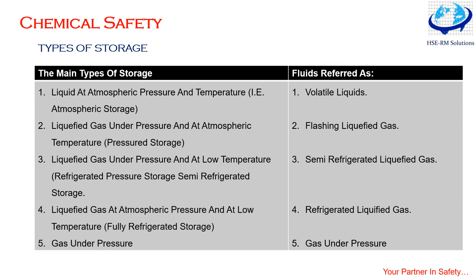Fifth is gas under pressure. A leak of volatile liquid stored under atmospheric conditions results in only slow evaporation. In the case of leakage of a chemical under pressurized storage condition, initial flash-off will occur and evaporation will be slow but faster than in the first case. In brief, the situation will vary depending upon the type of material stored. For economics, pressurized storage is preferred for small quantities, semi-refrigerated storage for medium to large quantities, and fully refrigerated storage for very large quantities.